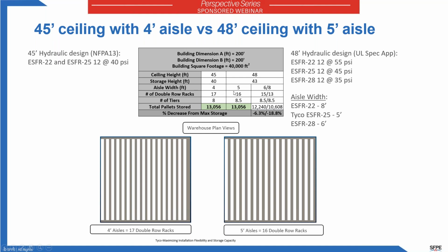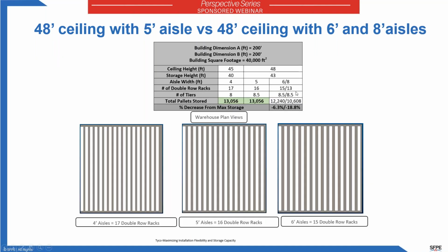As I noted, the Tyco ESFR 25 is approved with a 5-foot aisle. And what's interesting is that with the 5-foot aisle at 43 feet of storage, you can essentially have the same amount of storage capacity within the area as the ESFR 25 and 22 does with the 40 feet of storage height with the 45-foot ceiling. When you look at the different aisle widths that are approved with the 48-foot ceiling, you can see with the 6-foot aisle width, there's a reduction of about 6% capacity, and with the 8-foot aisle width, there's almost a 19% reduction in capacity.